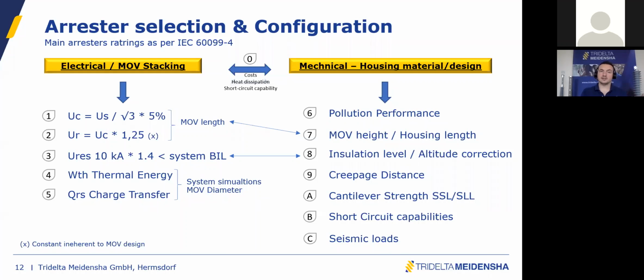You should start with the electrical part, but before, it also makes sense to understand the advantage of the different designs. As I said, the cage design is a cost-effective solution. It also provides better heat dissipation, which has important features for the protection level. And if you have extremely high short circuit capabilities or seismic requirements, you're going to look more at the tube design, for example. So from that perspective, you have already selected the type of housing that you need.